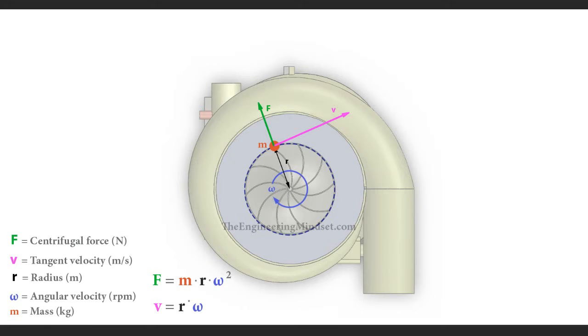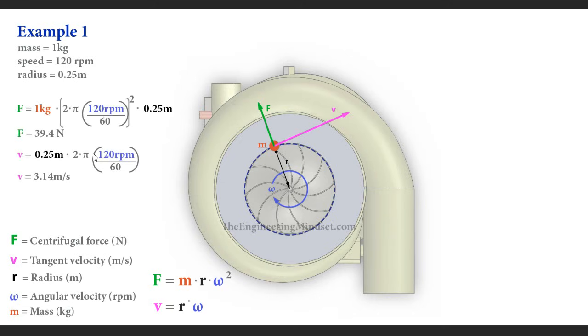But let's have a look at some examples. Let's say the refrigerant has a mass of 1 kilogram. The impeller is rotating at 120 RPM, revolutions per minute, and the impeller has a radius of 0.25 meters. So this is the formula and the calculations you would use to work out the centrifugal force and also the tangent velocity. As you can see, if we had 1 kilogram rotating at 120 RPM, this would result in 39.4 newtons, and that would also result in 3.14 meters per second as a tangent velocity. So what happens if we double the radius of the impeller?